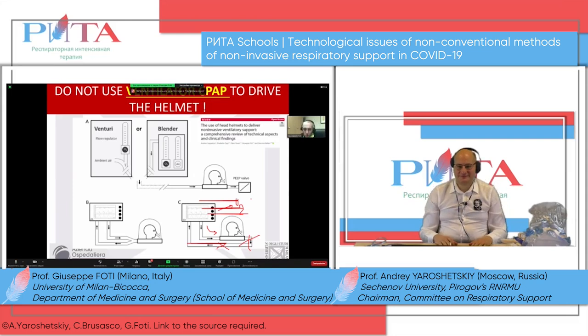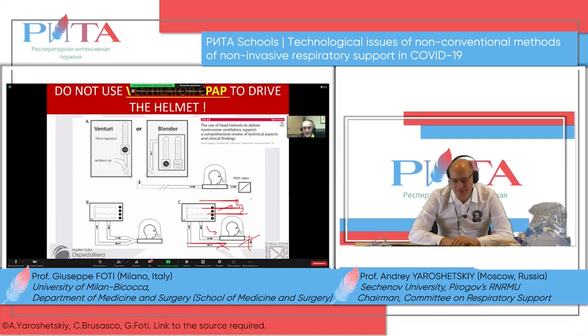So what to do is provide enough flow, around 60, 80, 90 liters, as Claudia suggested - not too high, doesn't provide too much noise, but provides a very good clearance. A compromise, as always in life. In my opinion, a flow around 80, 90 liters per minute is okay for the vast majority of patients.